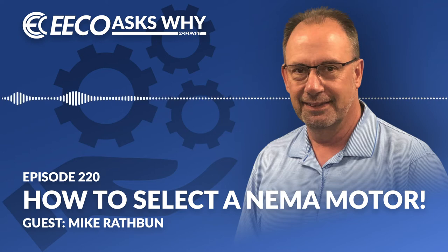Right, absolutely. And just to keep on this, what are some of the common mistakes that you've seen people make when it comes to specifying the right NEMA low voltage motor? I think what we've already discussed is the enclosure rating. Like I touched upon already, in a heavy environment, you're going to be more required to use a severe duty or an 841 motor. So making sure that the enclosure rating suits the environment is definitely at the top of the list. Then the design rating, that we're matching the application, and whether the frame is appropriate for the mounting requirements. Any of those factors associated with that nameplate that we've already touched upon would all be critical in ensuring the life cycle of that motor.